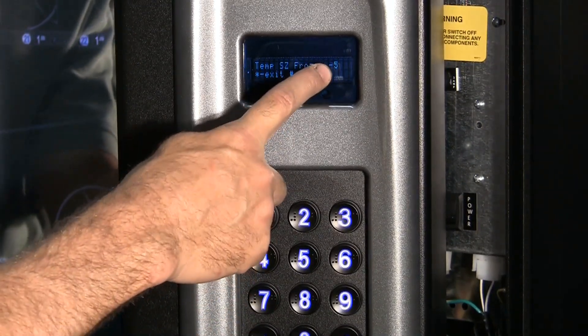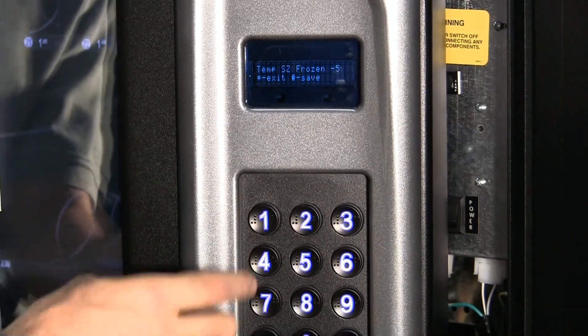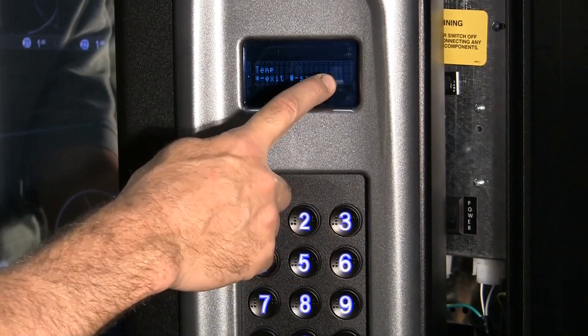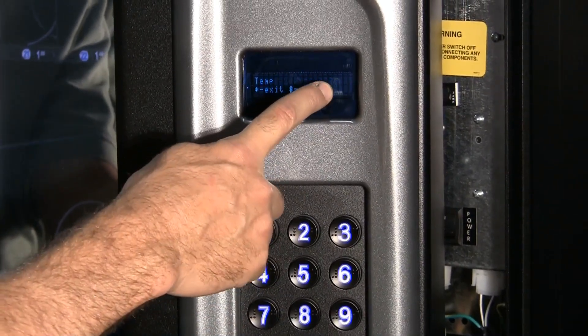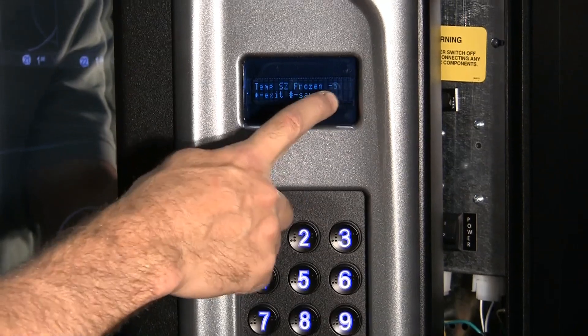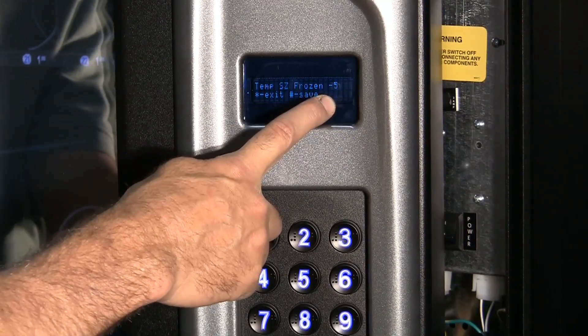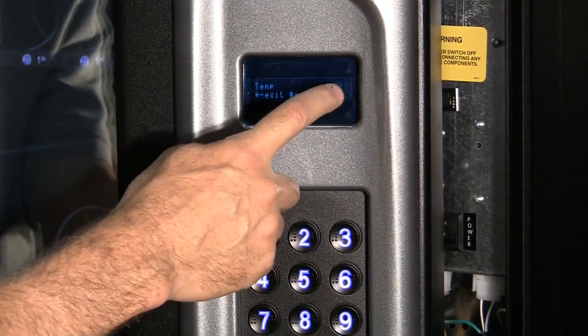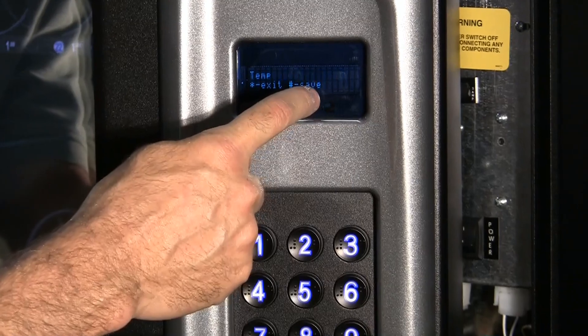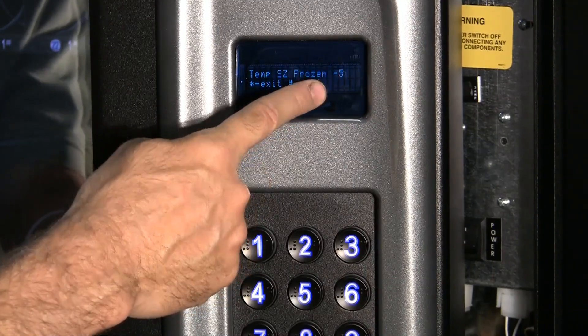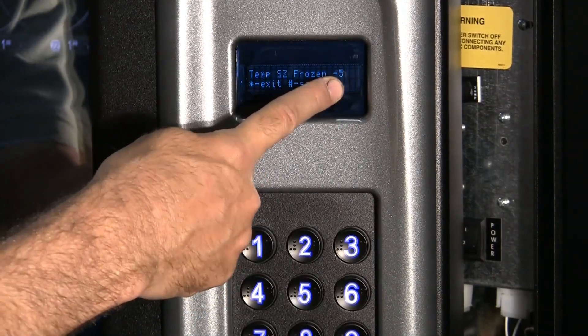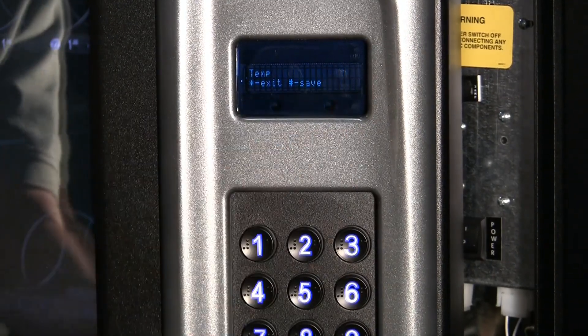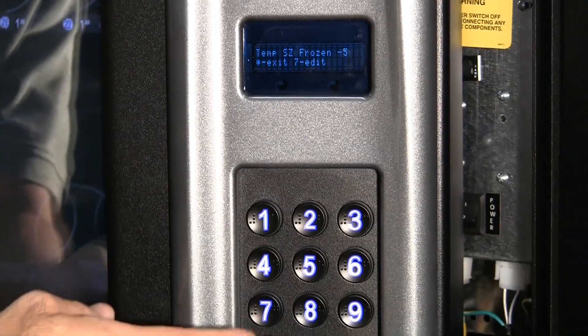And keep thumbing through until you get the single-zone frozen. Here we're at single-zone frozen minus five. There's a minus two. And there's one with no number at the end. And all it is, that's a minus 15 setpoint. The minus two is a minus 12 setpoint. And the one without a number is minus 10 setpoint. So we'll save it on minus five here.